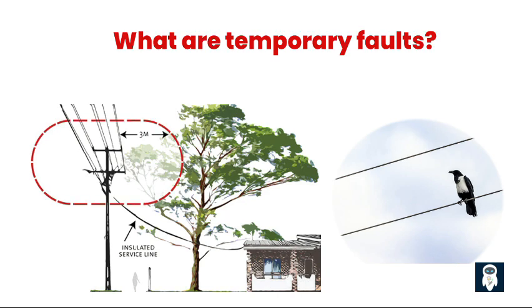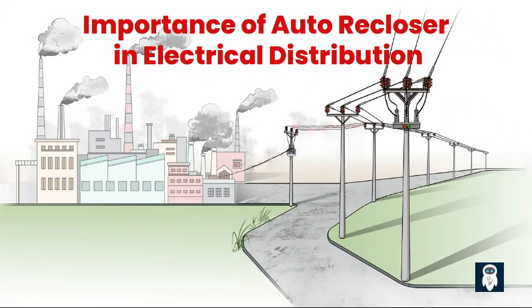Based on statistics and observations, the need for a trip-and-reclose function was readily recognized. If the line could be tripped open momentarily, then a subsequent reclosure very likely would be successful because, by then, the cause of the fault would be gone. Thus, the automatic circuit recloser, in providing this trip-and-reclose function, virtually eliminates prolonged outages on distribution systems due to temporary faults or transient overcurrent conditions. The auto-recloser plays a crucial role in maintaining a reliable and uninterrupted power supply.